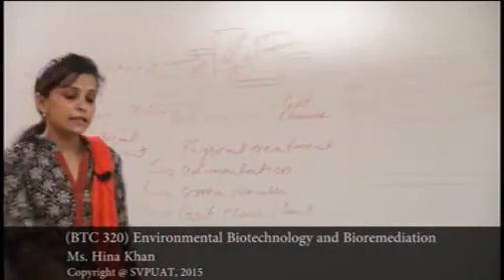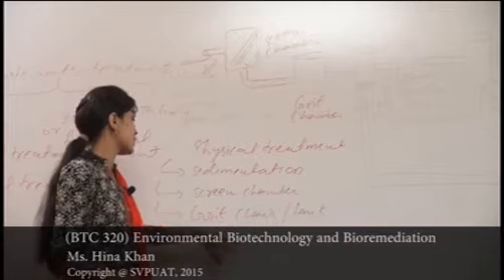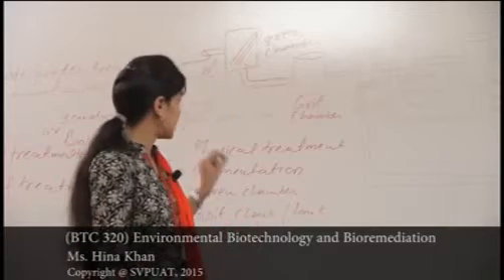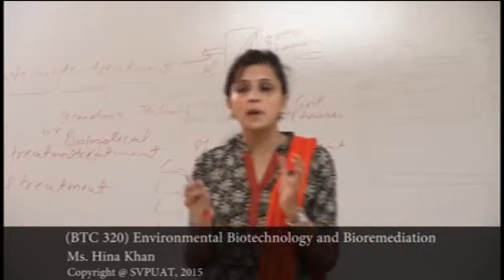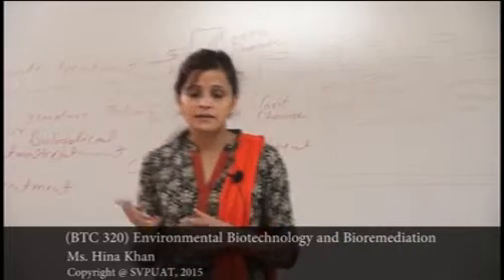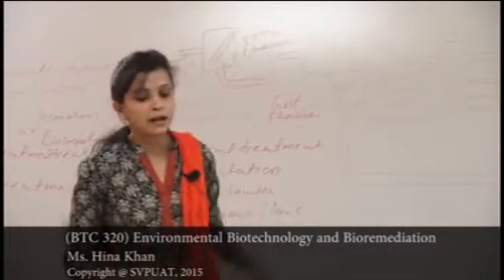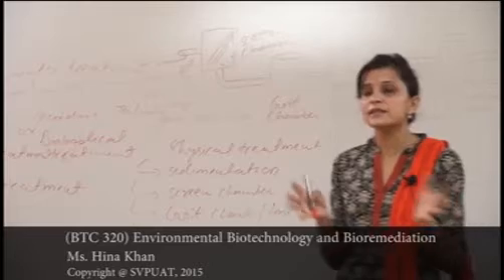Now we discuss these physical treatment techniques one by one: sedimentation, screen chamber, and grit chamber. In primary treatment, solid suspensions and flocculating material are removed. When wastewater passes through a screen, certain materials like wood pieces, plastic, paper, and floating debris are removed. The water then passes into a settling tank where it remains for a long time, allowing suspended particles to settle — a process known as sedimentation.